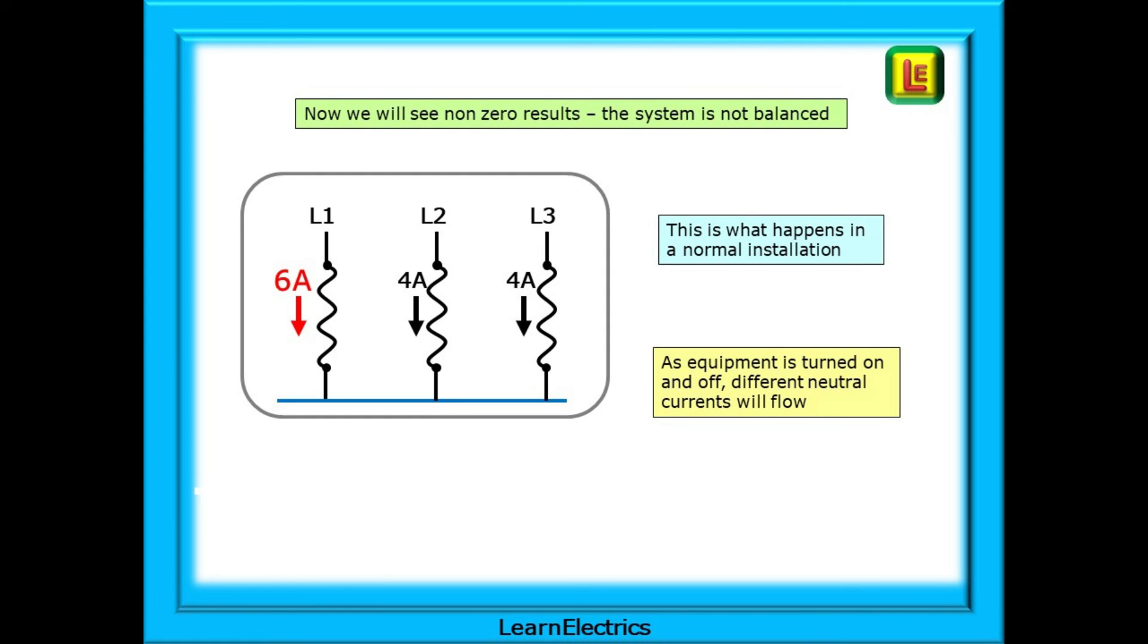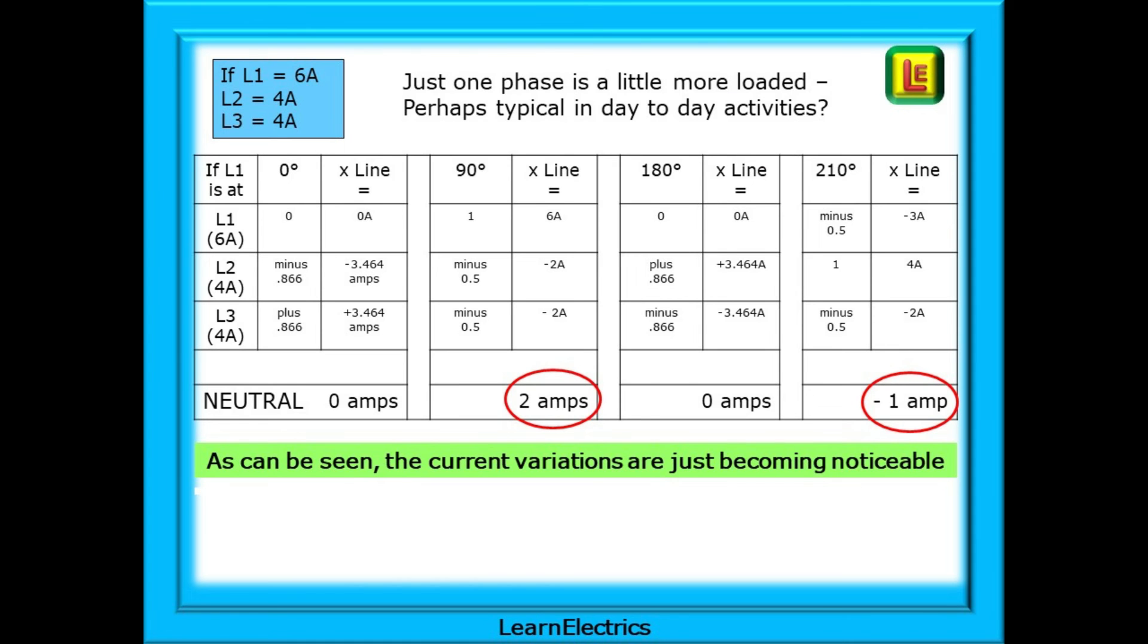We never have a perfectly balanced world. As the equipment is turned on and off during the day, different neutral currents will flow. Another heater is turned on, the kettle is used, the compressor is turned on. So here we have just one phase a little more loaded than the others. Using our table, we can see what effect this has on the neutral currents. As shown here, the imbalance at 90 degrees is 2 amps, and at 210 degrees, it is 1 amp. The current variations are just noticeable, and considering that this is with 14 amps total current down the three line conductors, this is not a problem for day-to-day activities.